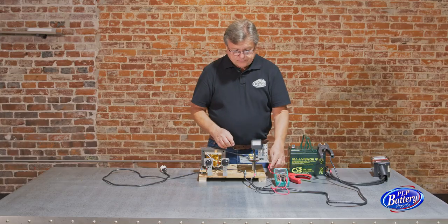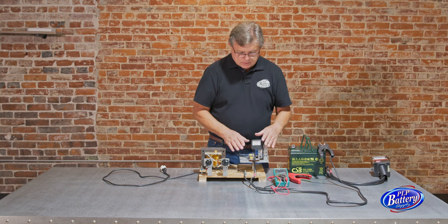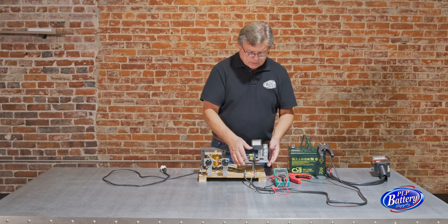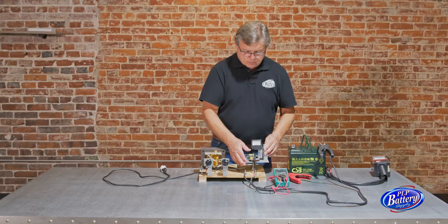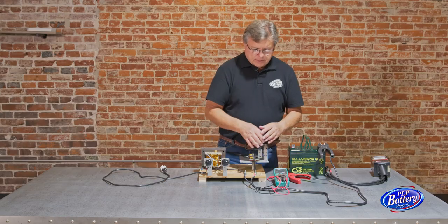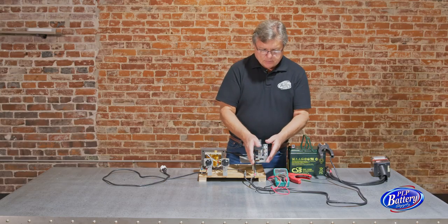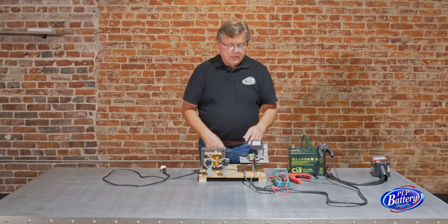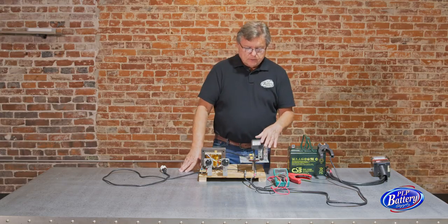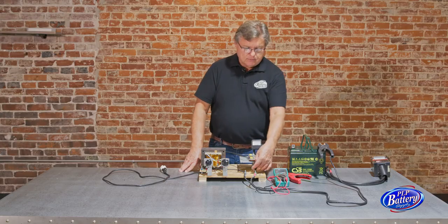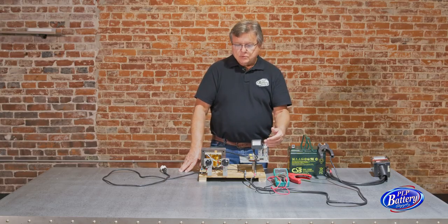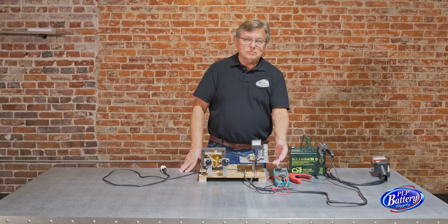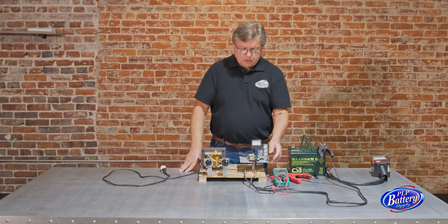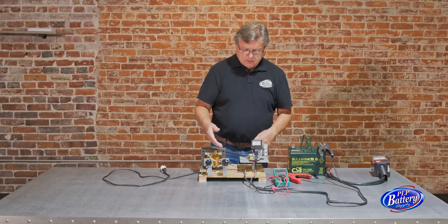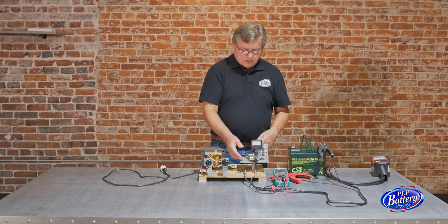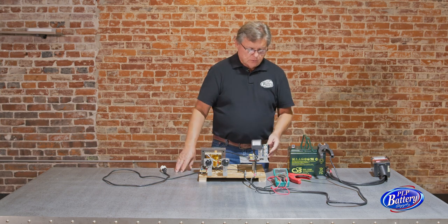So with that test, what it's going to tell us is that all the components, from the rectifier to the breakers to the meter, everything that has to do with the DC output, that's all working. If one of those voltages failed us, and actually at this point, there's not going to be a situation where we're going to have one failure. They're going to all be low, because from this point on, they're all using the same thing. Whatever the voltage is coming into the rectifier, it'll be reflected in what's going out.